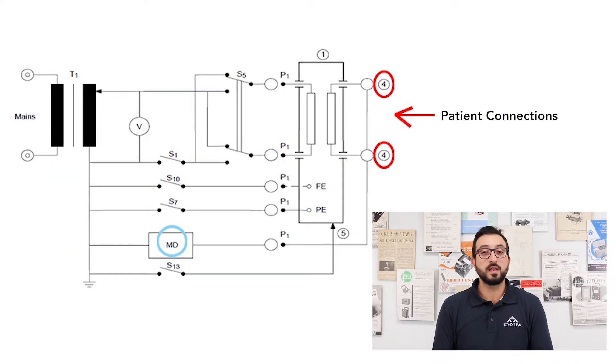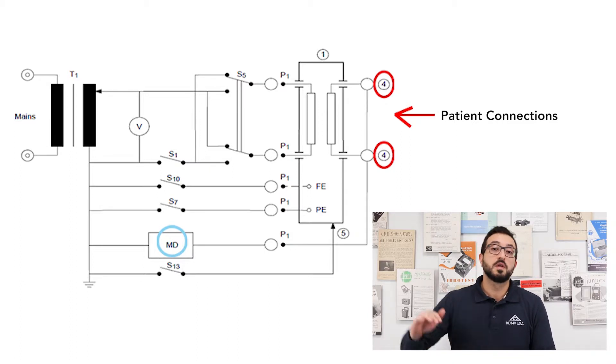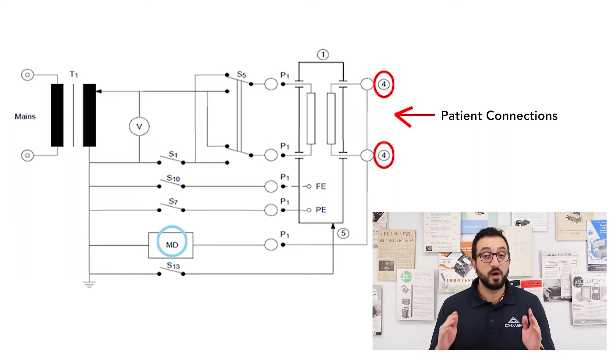So let's take a look at how the medical device standard requires us to measure patient leakage, and in doing so we're going to take a look at two different examples. The first one is for a single patient connection, and we're going to measure the leakage current flowing from that patient connection, going through the measuring device circuit which is simulating the human body impedance, and back to reference or ground.